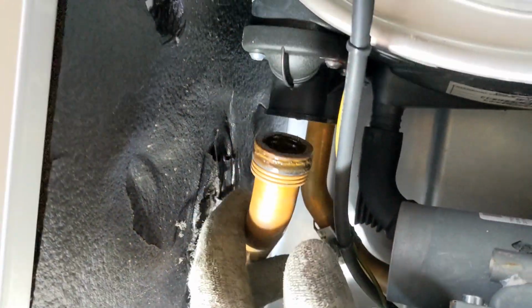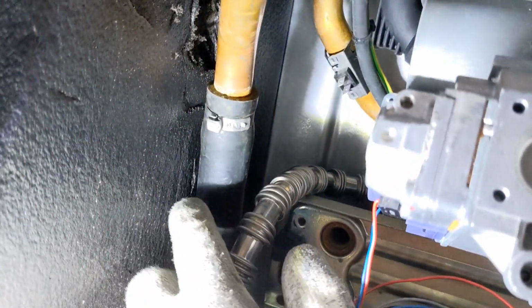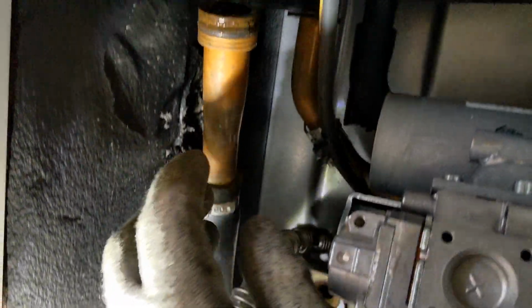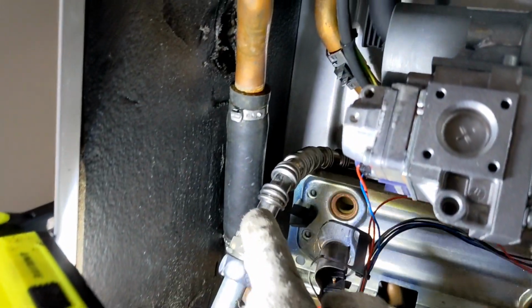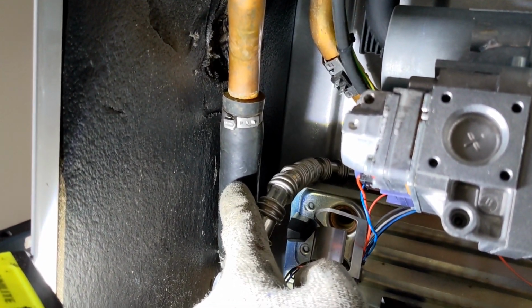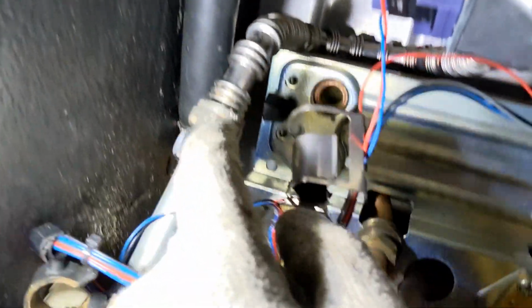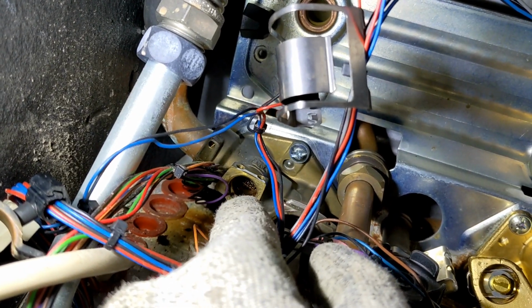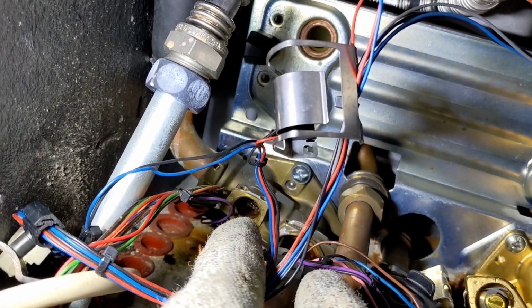I normally take it out from the main heat exchanger side first because you've got a bit of flex on the rubber hose there, so you can wiggle it and tease it down. Just try not to crunch that rubber too much, otherwise all the muck in there will make its way down into the filter and block up all around there.